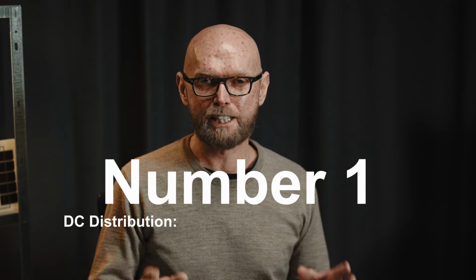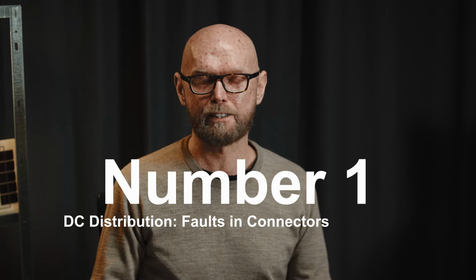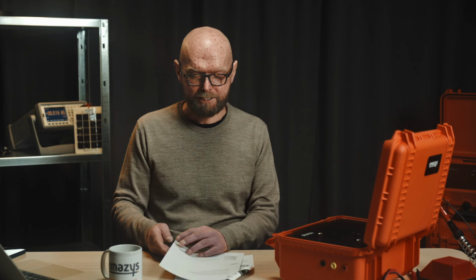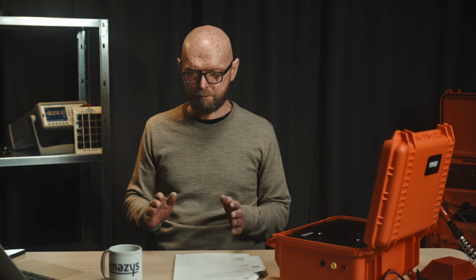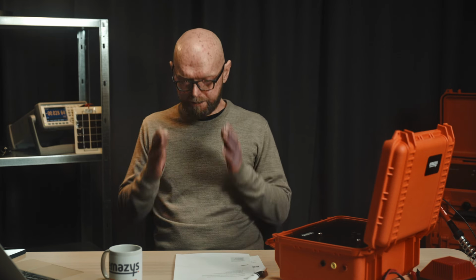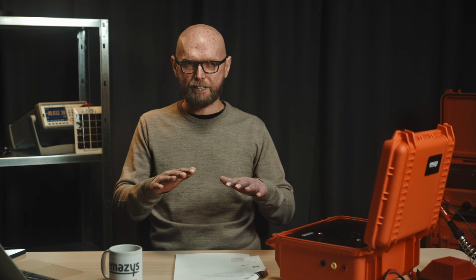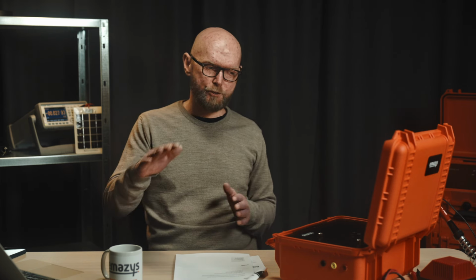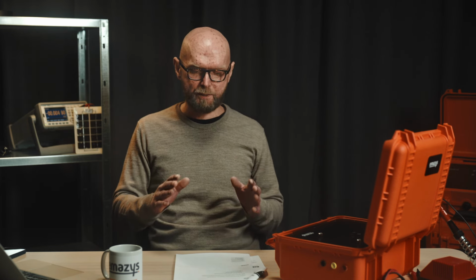Number 1, DC distribution, faults in connectors and cables. Actually, it's a bit surprising because normally when a new technician goes to the field, he is to some extent taught that homogeneous power degradation in the solar panels is the most common fault, because we have this idea that when you install a power plant, then after 20 years, the efficiency of that power plant is just slowly degrading over time. But when we look into it and actually do some investigative work, we see that it is not homogeneous production loss that is the main problem out there.